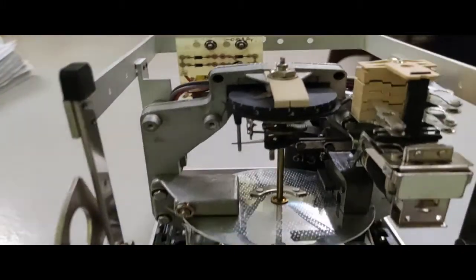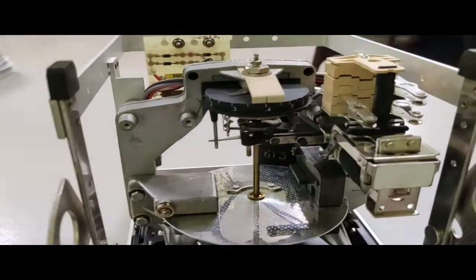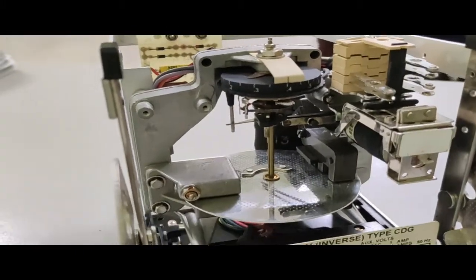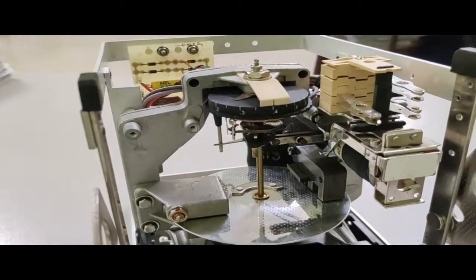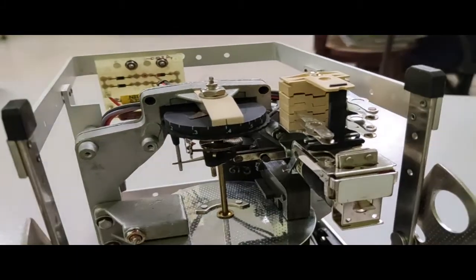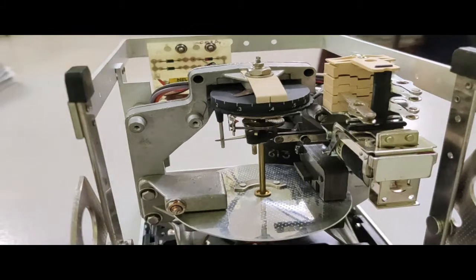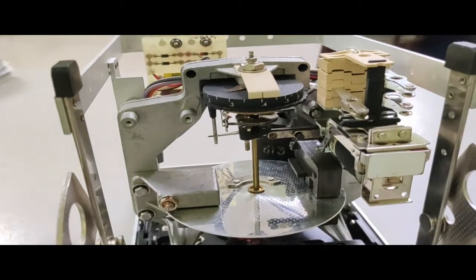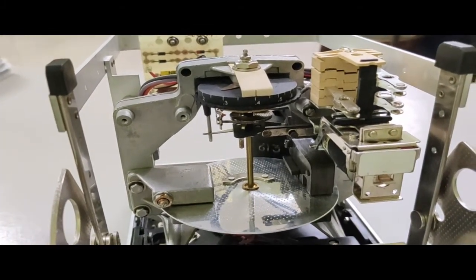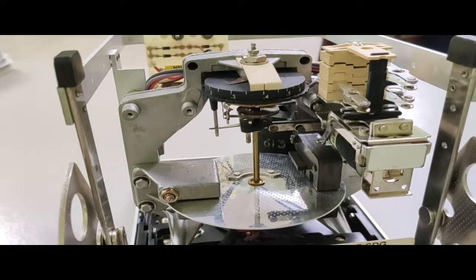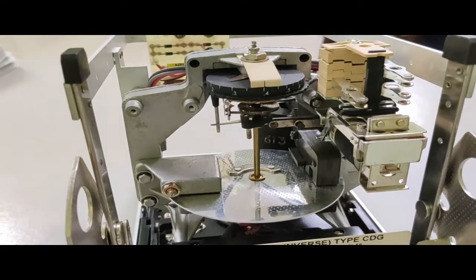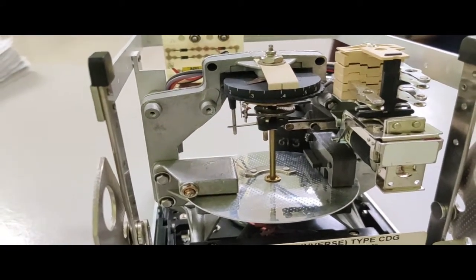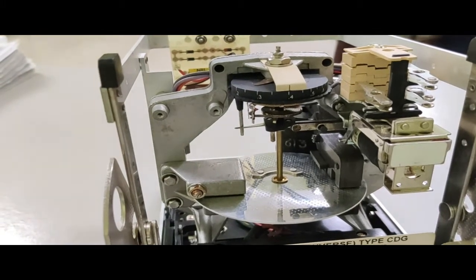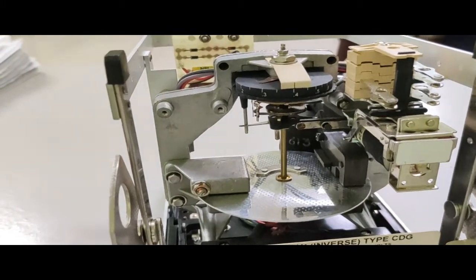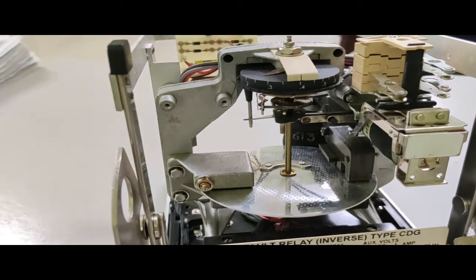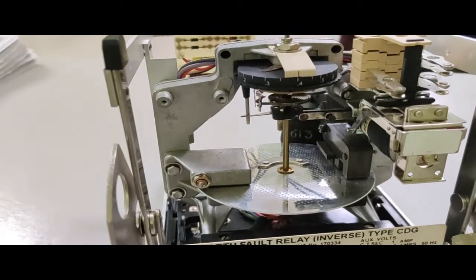So whatever apparatus is there must be able to accept that current in that short time. It's a very small time, in milliseconds obviously, a few cycles. So in that time if the relay generates the trip signal, then the circuit breaker unnecessarily trips the line. Then after some time, if the fault is cleared, you need to send some personnel to the circuit breaker, and they need to reconnect it. So some time is wasted beyond that. That's why intentional time is given.